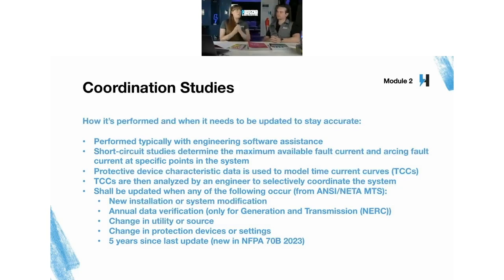And when does it need to be updated? Guess what? It's going to be pretty similar to what we've been saying so far. Yes, at a minimum of every 5 years, or if something has changed to make it no longer adequate. It's not up to date anymore. The MTS is helpful. It very much is. I'm telling you, honestly, anytime you have a different type of fuse, anytime you've adjusted a setting on a breaker or replaced it, if you have different impedance components, lots of things could change and make your coordination study potentially false. Right.